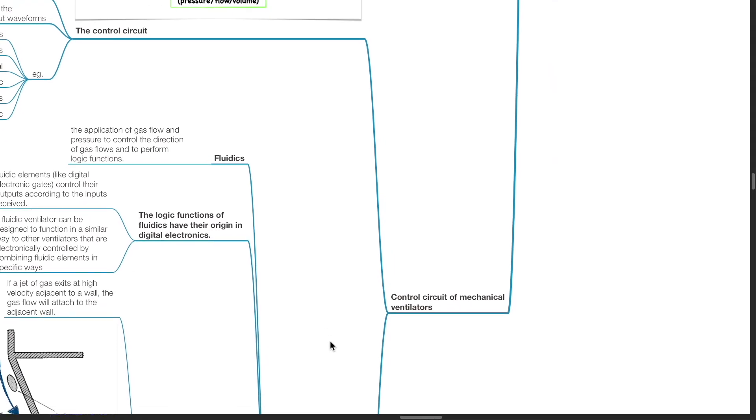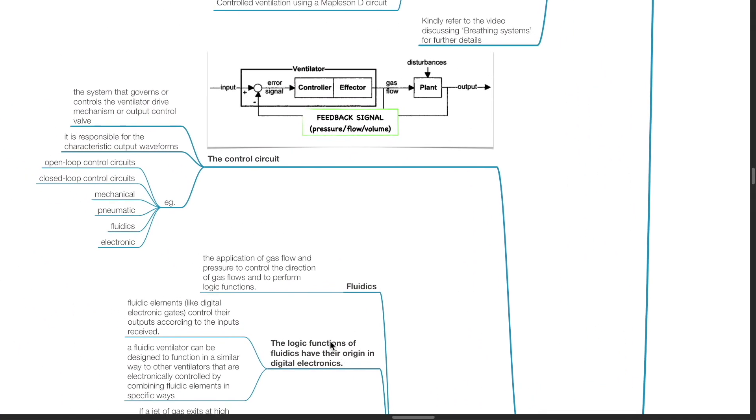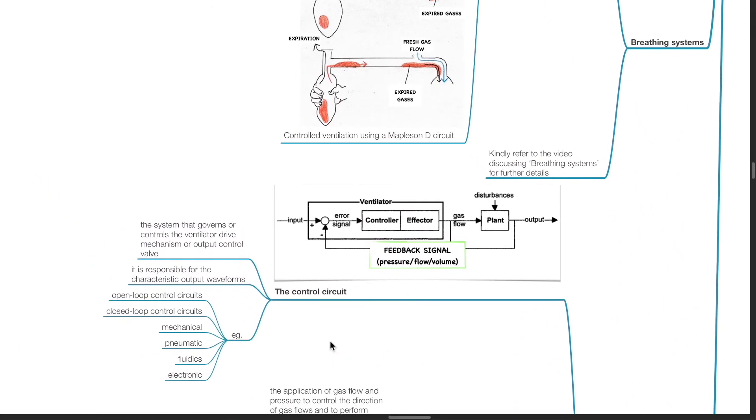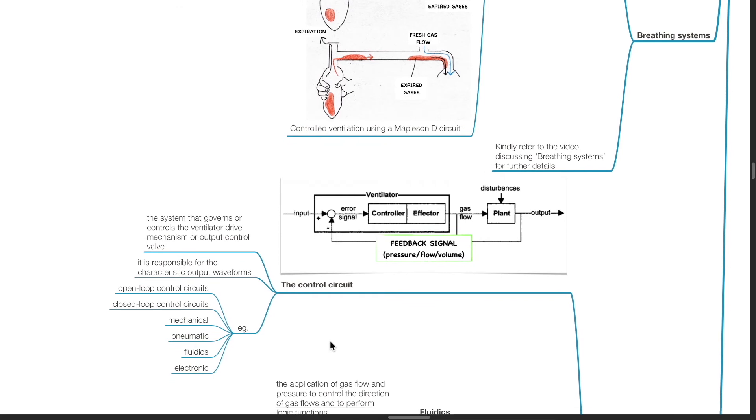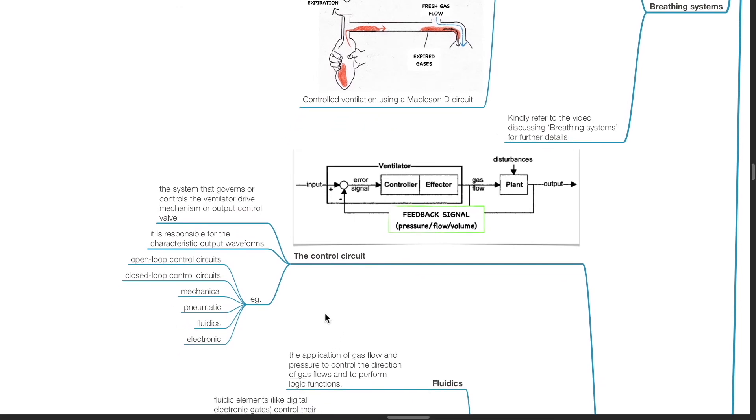Control circuits of mechanical ventilators. The control circuit is the system that governs or controls the ventilator drive mechanism or output control valve. It is responsible for the characteristic output waveforms.